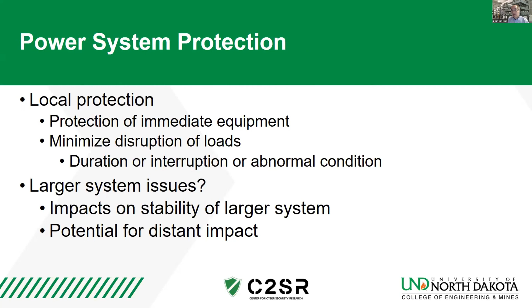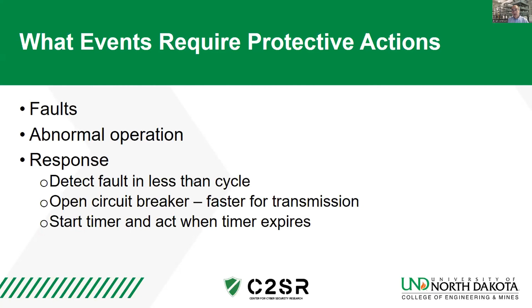Normally we want protection responses to faults and abnormal operating conditions, and the expectation is usually that the relay is going to detect the fault in less than a cycle, so in about 15 or 16 milliseconds, and then it will send a command to open a breaker. At the transmission level, you may have the detection and the breaker open in 30 to 50 milliseconds. At distribution, it's generally a little bit slower, so you may be getting into hundreds of milliseconds in response for a lot of systems.